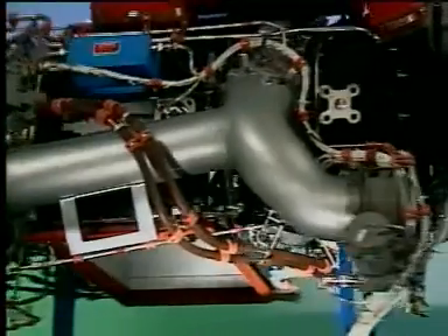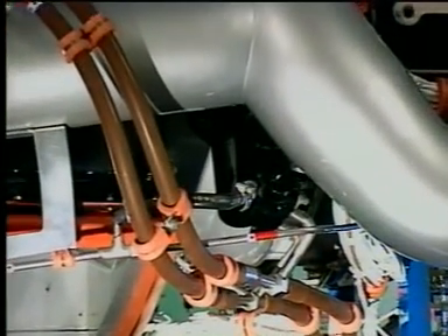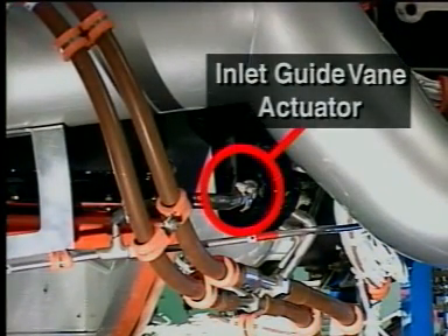The airflow through the load compressor is controlled by internal inlet guide vanes and the inlet guide vane actuator. The inlet guide vane actuator is located at the 8 o'clock position on the load compressor housing. It's operated by high-pressure servo fuel and is controlled by the electronic control box.